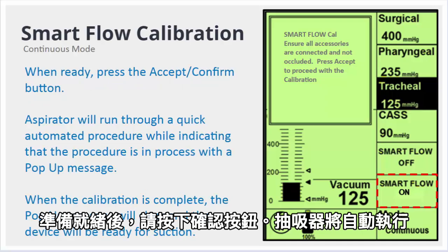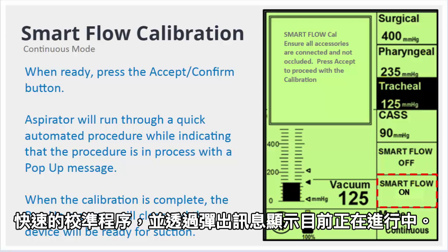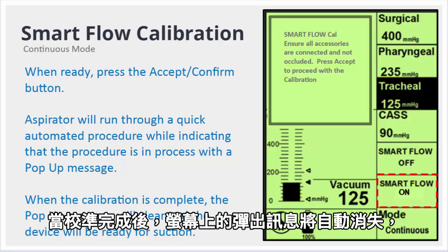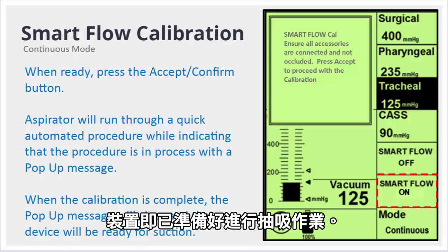The aspirator will run through a quick automated procedure while indicating that the procedure is in process with a pop-up message. When the calibration is complete, the pop-up message will clear from the display and the device will be ready for suction.